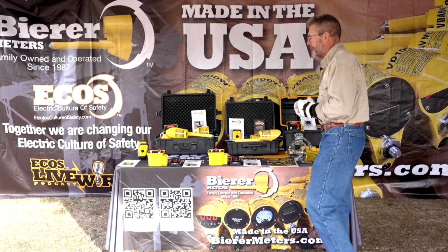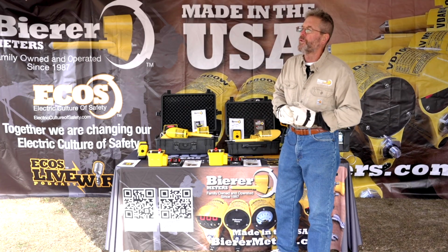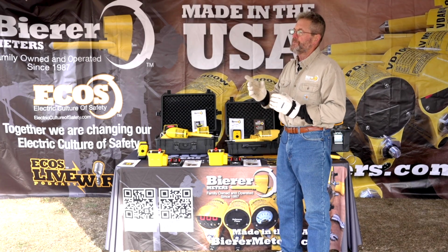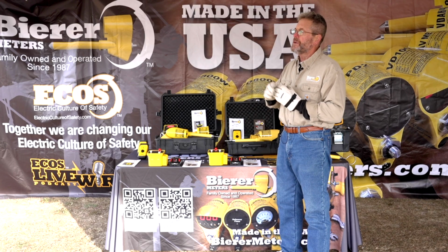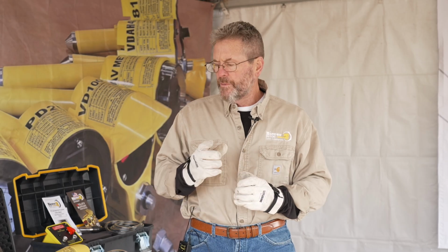For the portable power supplies, Bierer Meters recommends that you perform a live test before you use your testers, on a live known voltage source, so when you go to that conductor you can verify if it's energized or de-energized. We want to make sure your tools are working out in the field. We have 3 power supplies, and the applications of each are a little different, so make sure your specific tool is matched up to the capabilities of one of these 3 power supplies.